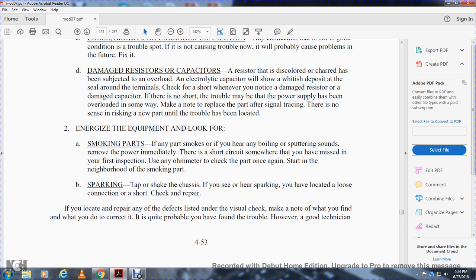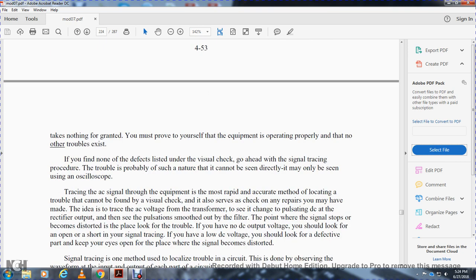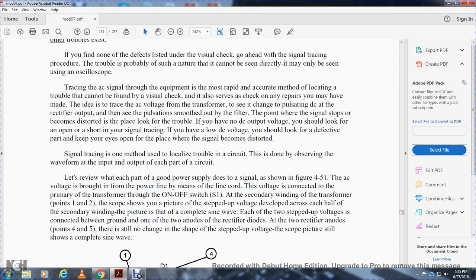After visual check, energize the equipment and look for smoking parts. If you see smoke or hear a boiling or hissing sound, remove power immediately — there is a short circuit somewhere. If you locate sparking, you have found a loose connection or short — check and repair. After correcting defects found in the visual check, verify the equipment is operating properly and no other troubles exist. If no defects are found visually, proceed to signal tracing. Signal tracing is the most rapid and accurate method of locating trouble that cannot be found visually — tracing AC through the transformer, then pulsating DC through the rectifier, then filtered DC through the filter stages.